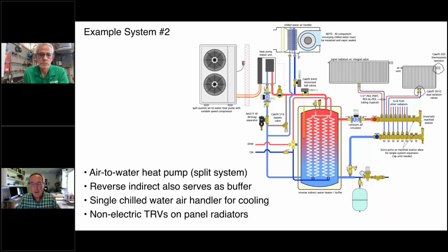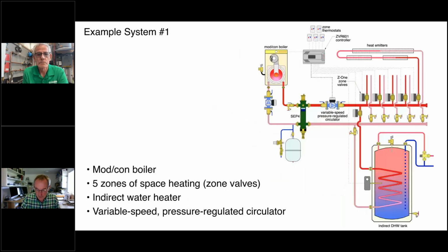What we don't want to do is break up the stratification in this tank. If we just circulate this fluid, but without putting heat in it, we're going to break up this temperature stratification. So instead of doing that, both of these valves would be closed and the flow will simply go through the differential bypass valve, up through the separator, and then right back into the heat pump. So think of that as kind of a holding pattern until the temperature comes up. And once it comes up to the temperature equal to or slightly above the tank temperature, we open this valve and the flow goes right over there. Same thing for cooling. So that's one.